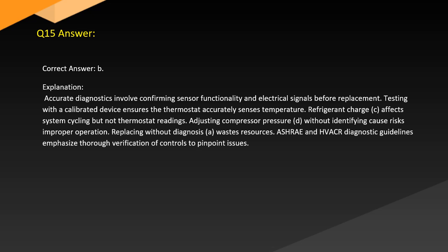Answer. Correct answer: B. Explanation: Accurate diagnostics involve confirming sensor functionality and electrical signals before replacement. Testing with a calibrated device ensures the thermostat accurately senses temperature. Refrigerant charge, C, affects system cycling but not thermostat readings. Adjusting compressor pressure, D, without identifying the cause risks improper operation. Replacing without diagnosis, A, wastes resources. ASHRAE and HVACR diagnostic guidelines emphasize thorough verification of controls to pinpoint issues.